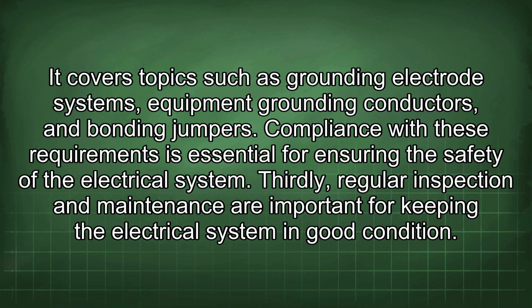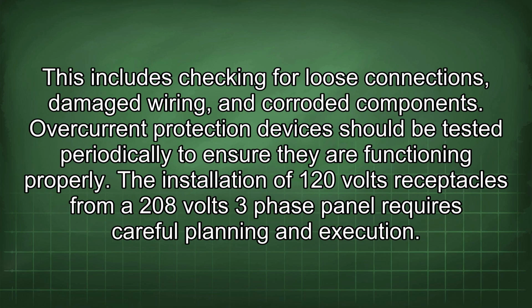Thirdly, regular inspection and maintenance are important for keeping the electrical system in good condition. This includes checking for loose connections, damaged wiring, and corroded components. Overcurrent protection devices should be tested periodically to ensure they are functioning properly.